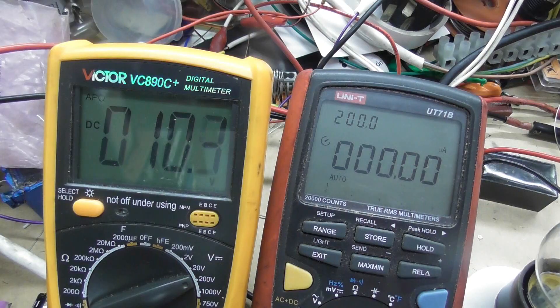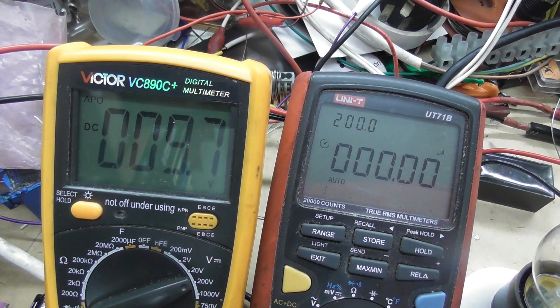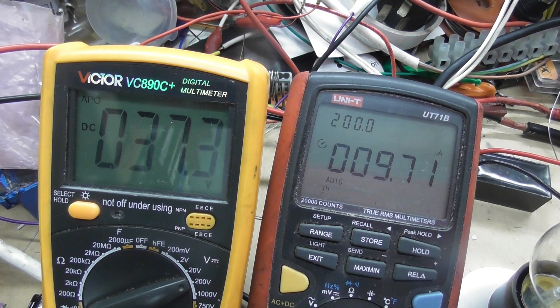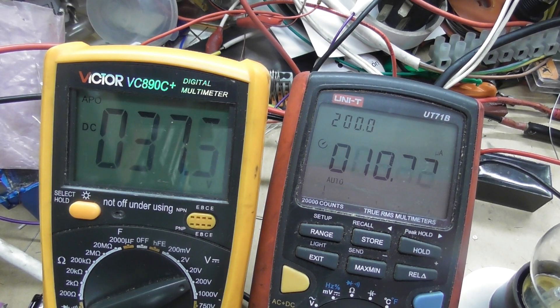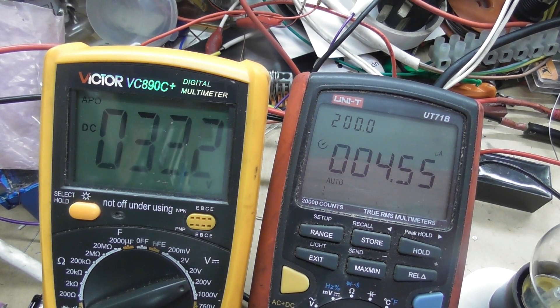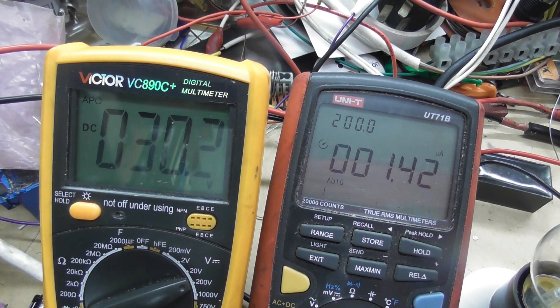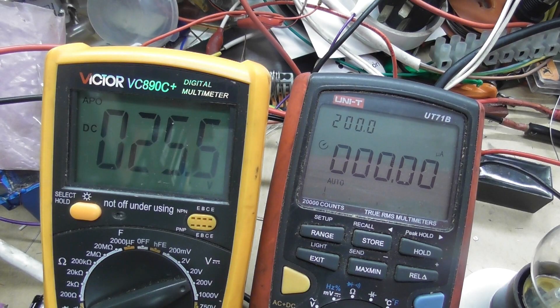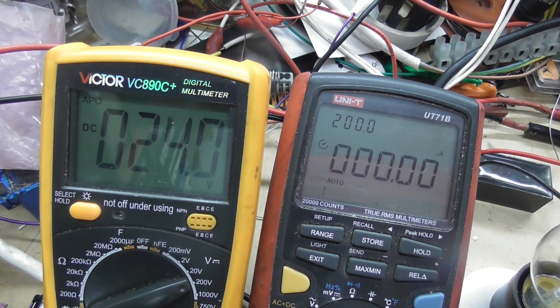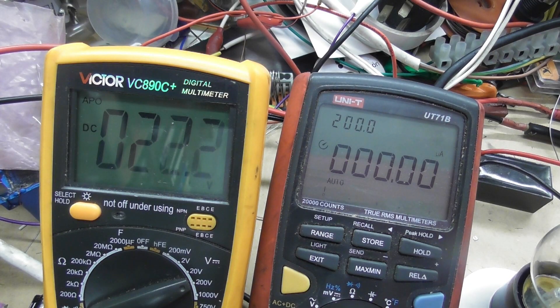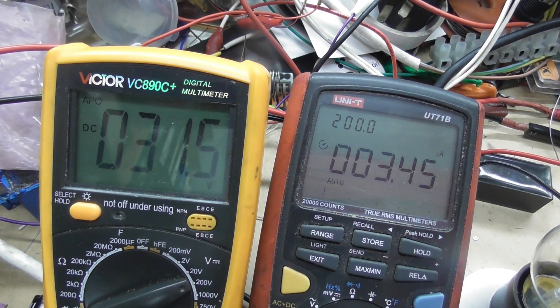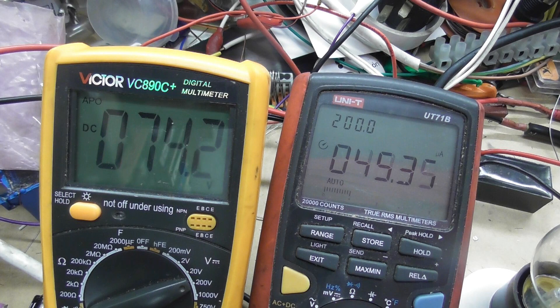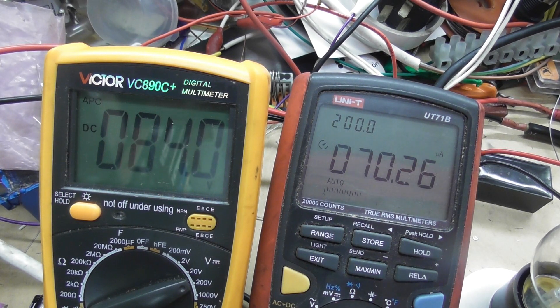So I'm going to ramp this voltage up to the 125 volt SEL device, start conducting and passing current. It's 30 volts. I'm ramping it up to 125 volt DC, and it's still just leakage current.